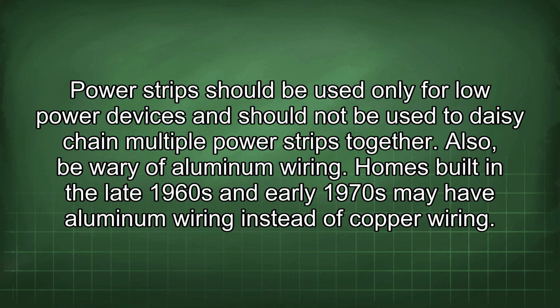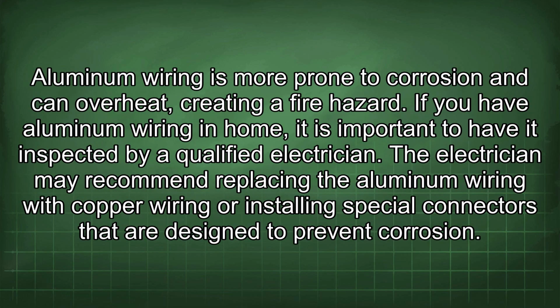Homes built in the late 1960s and early 1970s may have aluminum wiring instead of copper wiring. Aluminum wiring is more prone to corrosion and can overheat, creating a fire hazard. If you have aluminum wiring in your home, it is important to have it inspected by a qualified electrician. The electrician may recommend replacing the aluminum wiring with copper wiring or installing special connectors that are designed to prevent corrosion.